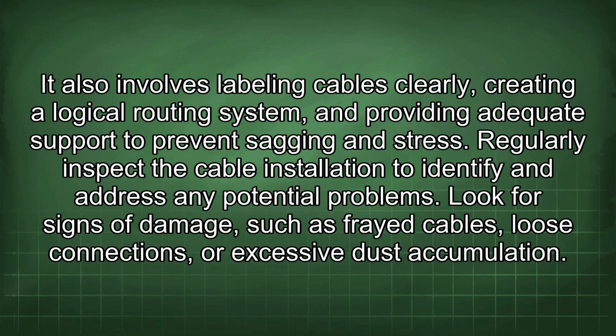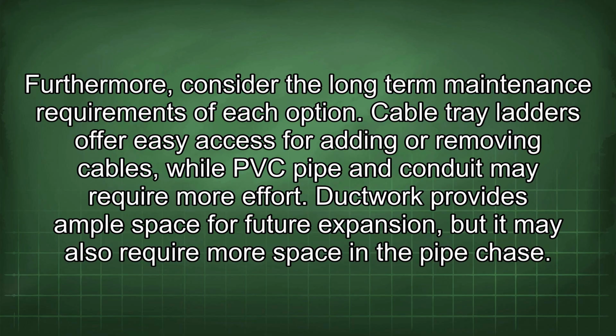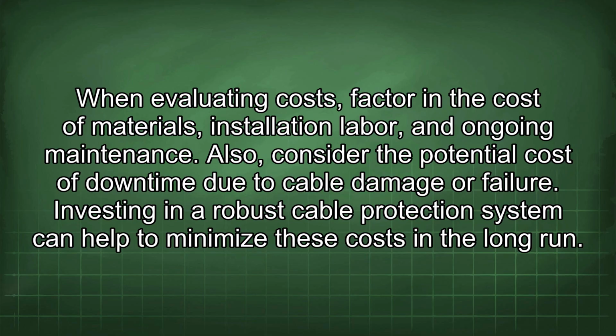Regularly inspect the cable installation to identify and address any potential problems. Look for signs of damage, such as frayed cables, loose connections, or excessive dust accumulation. Furthermore, consider the long-term maintenance requirements of each option. Cable tray ladders offer easy access for adding or removing cables, while PVC pipe and conduit may require more effort. Ductwork provides ample space for future expansion, but it may also require more space in the pipe chase. When evaluating costs, factor in the cost of materials, installation labor, and ongoing maintenance. Also, consider the potential cost of downtime due to cable damage or failure. Investing in a robust cable protection system can help to minimize these costs in the long run.